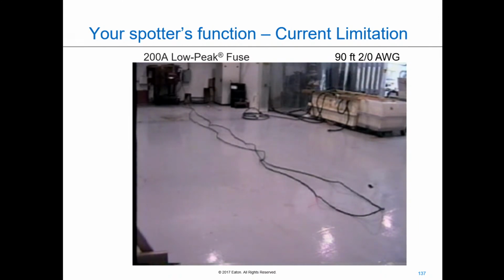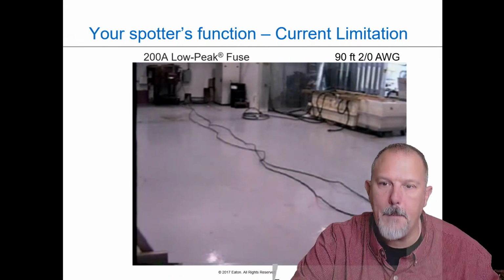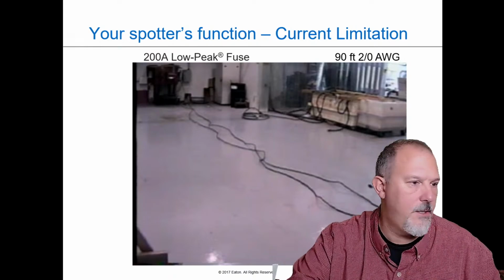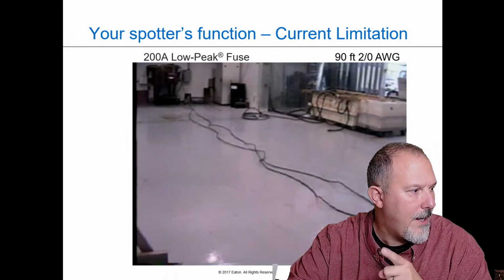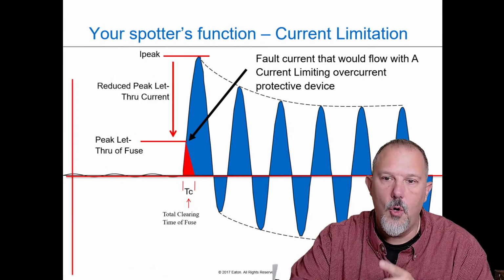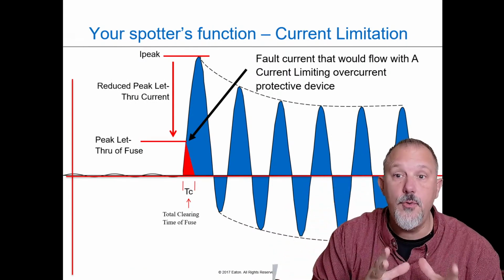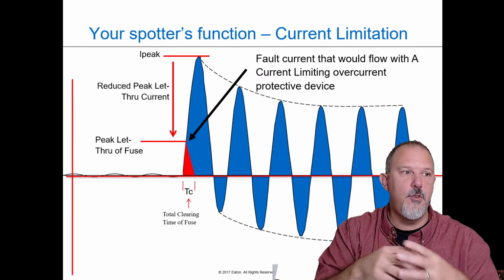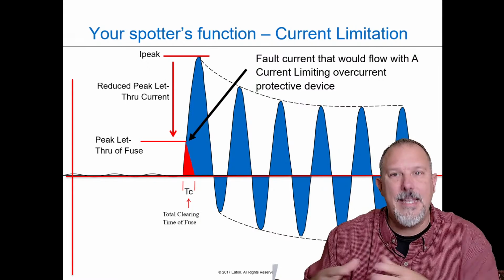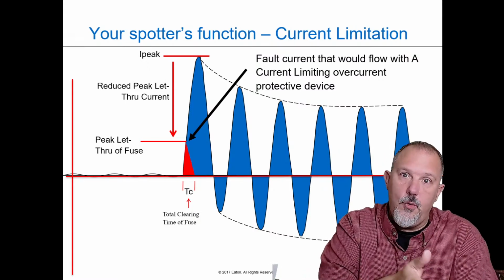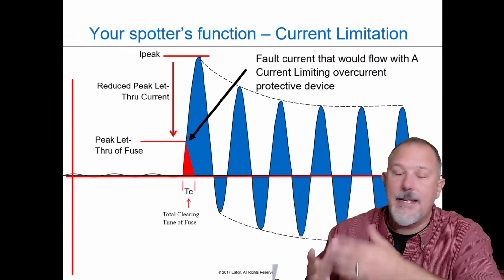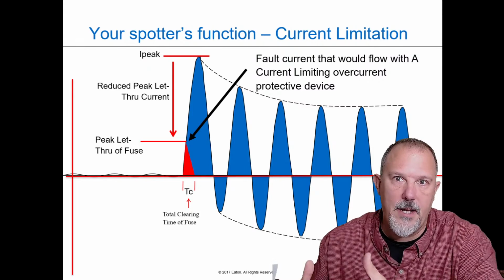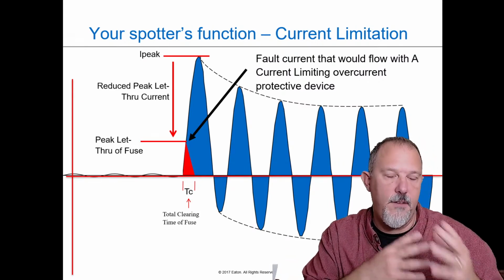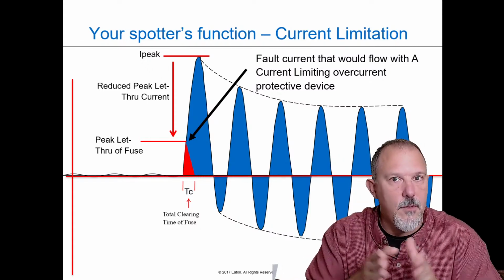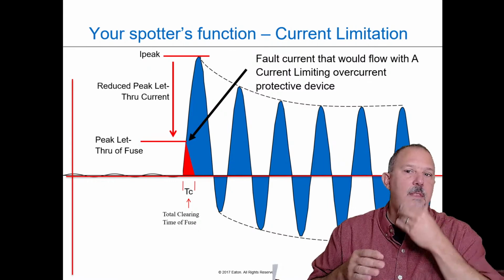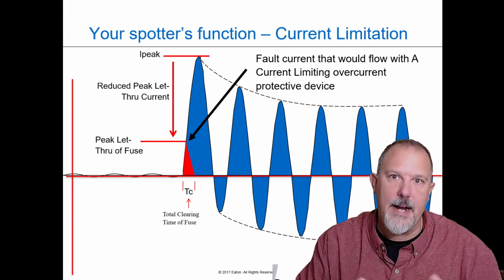It barely moves. Absolutely barely moves. And the reason is because I am taking that first half cycle from a doozy to just a little blip. I've removed the magnetic forces and I've removed the heat. So when we're protecting equipment, like that conductor, I'm protecting it from short circuits. How am I doing that? By what we just saw. I'm leveraging the power of current limitation. I've reduced the peak and I've reduced the amount of time I let it flow. So that makes sure I am providing protection.